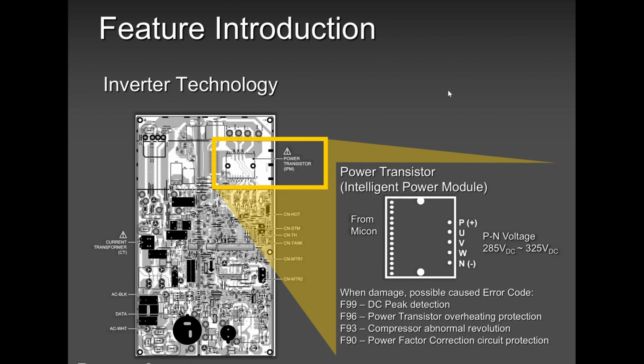So when that outdoor PCB is defective, you will get error codes like F99, F96, F93, or F90. But before you condemn this PCB, remember this, guys, please power reset for 15 to 20 minutes. I had a call over the Easter weekend, a gentleman from Ohio. He called me and he said, it's super cold today and I have this problem. I can't remember if it was an F96 or an F93, but one of these error codes. And I told him, please shut the power off for 5-10 minutes. Sorry, for 10 to 15 minutes and try it.